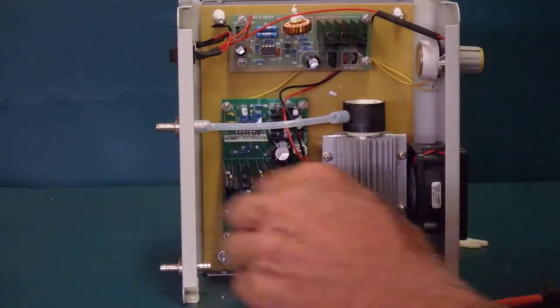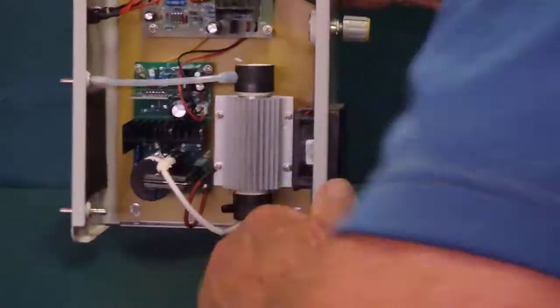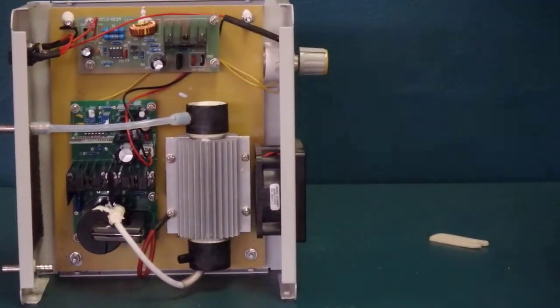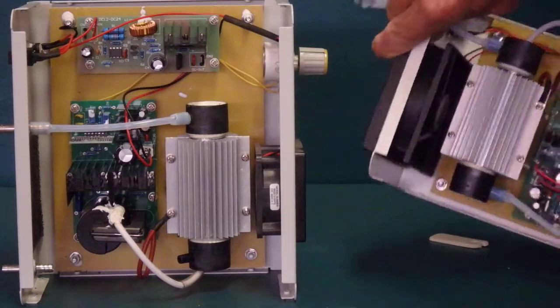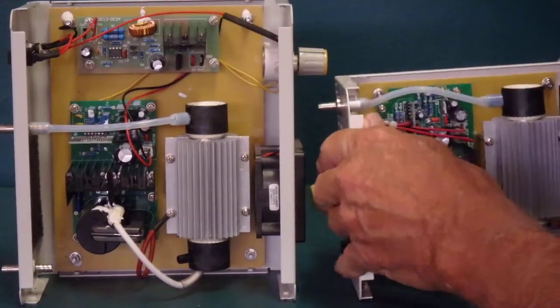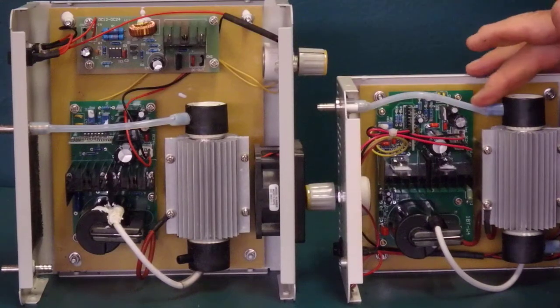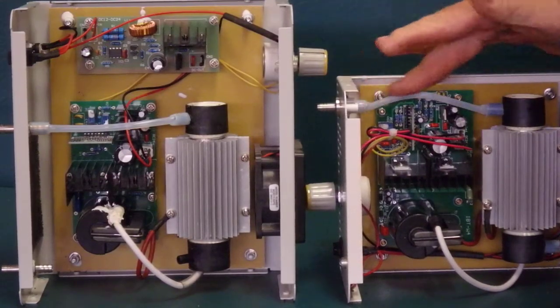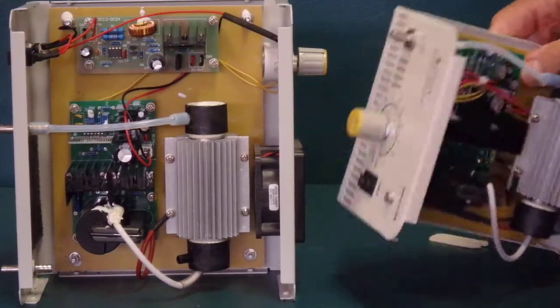Let's take a look at what the NLA-24 looks like when it has new tubing. Now we have the NLA-24 with new tubing in it. The oxygen side is not as critical, but if you replace it, you might as well just put it in both oxygen and ozone.